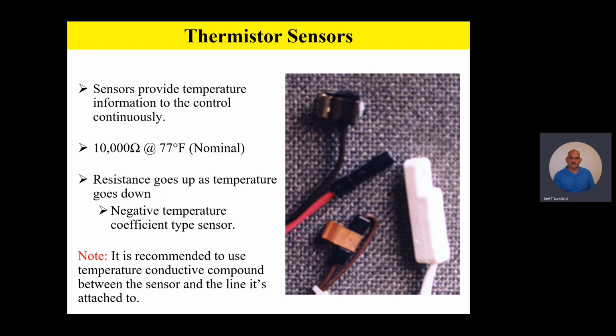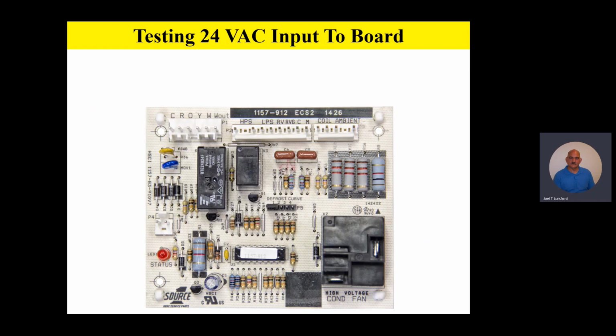Now, please note it is also recommended to use a temperature conductive compound between the sensor and the line it's attached to. This will help ensure that the sensor is reading the accurate temperature of the line, if it happens to be a line sensor or a coil sensor. So let's take a look at that control board at this time.